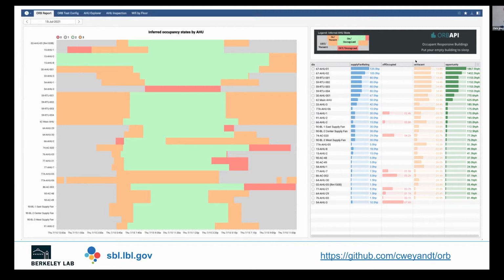Then to provide some actual metrics, we take the durations of each of these states for each air handler and put those into a chart that can be sorted by any of these 4 columns. The red zones we care most about are when the unit's off and we think somebody's actually there - we can see this 53 AHU3, 54 AHU3, that's this one.